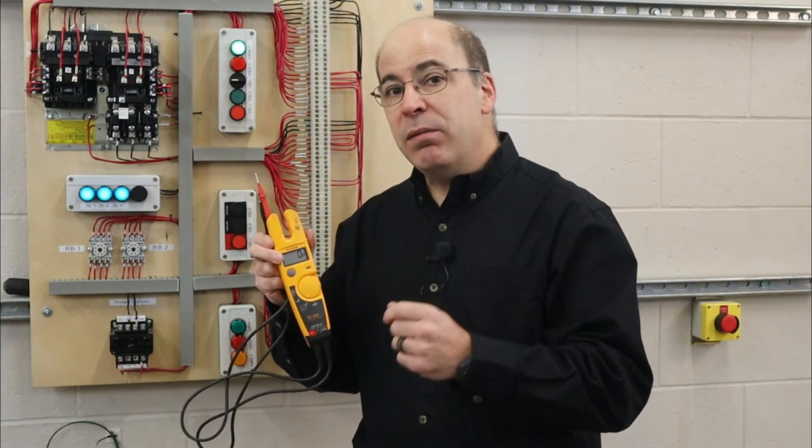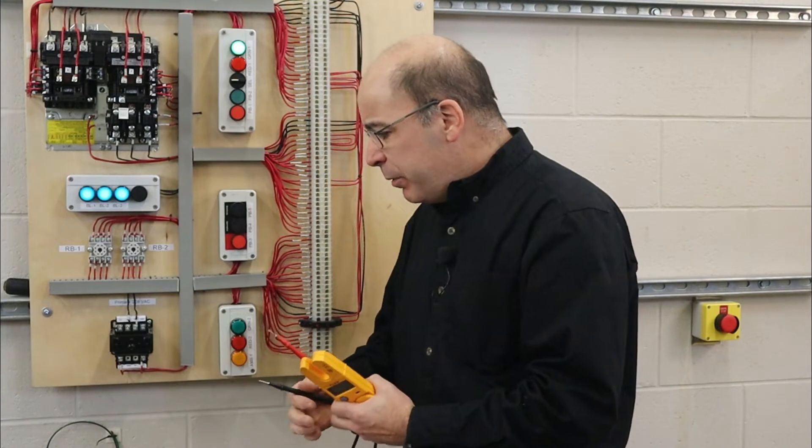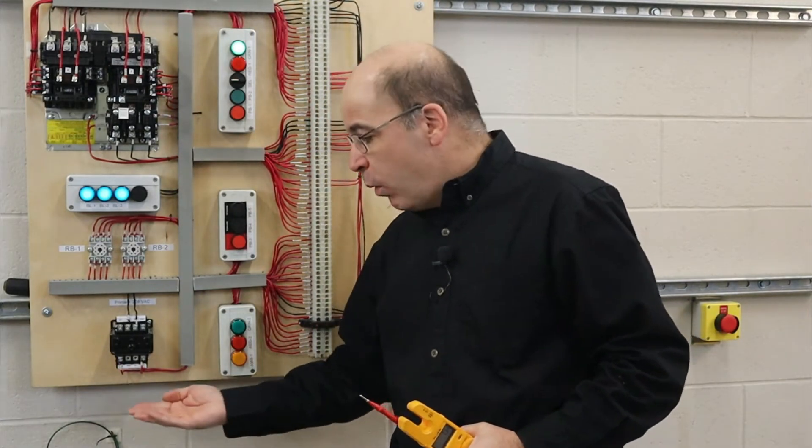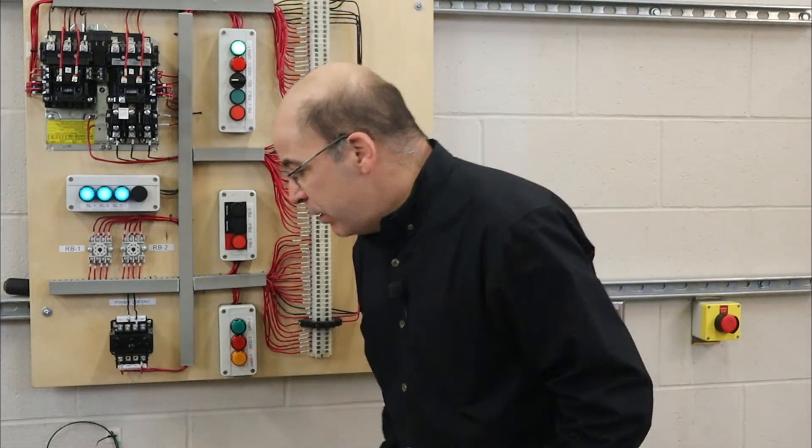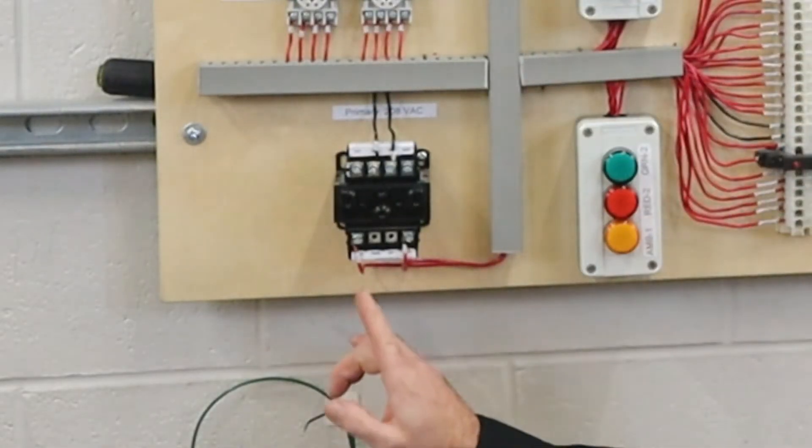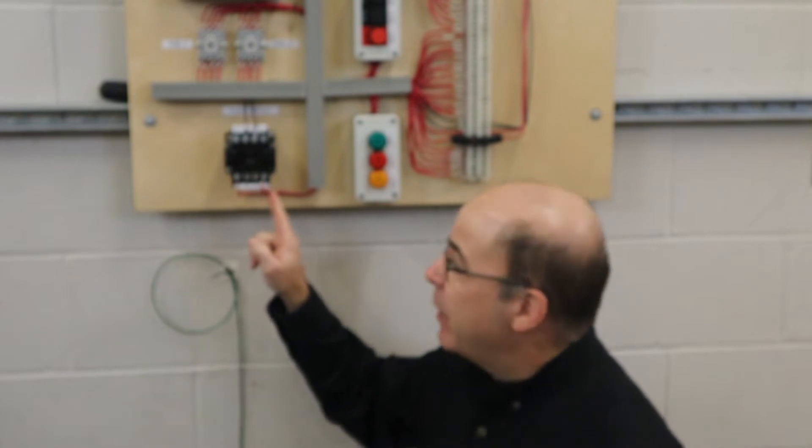How do we effectively take measurements when dealing with a system like this where we have a floating neutral? Now why do we call this a floating neutral? It's due to the fact that the transformer, the secondary, is not bonded. It's not going to ground. All we have is the leads on the secondary X1 and X2 respectively that are completing a circuit. That is known in technical terms as a floating neutral. It's unbonded.